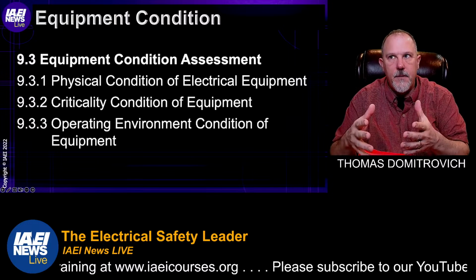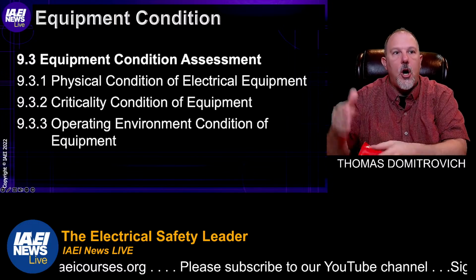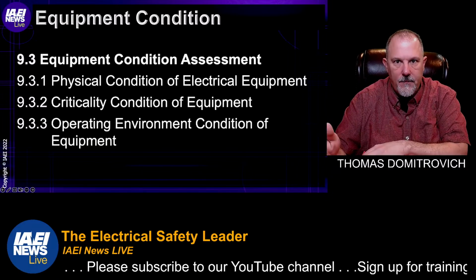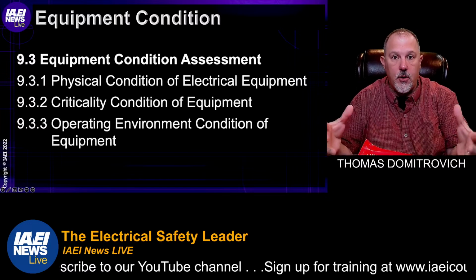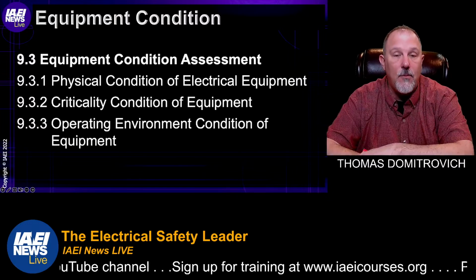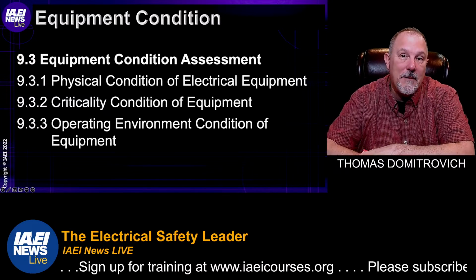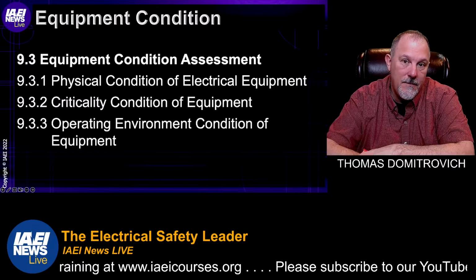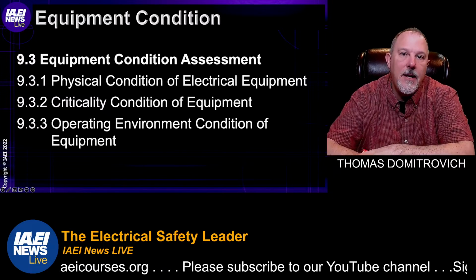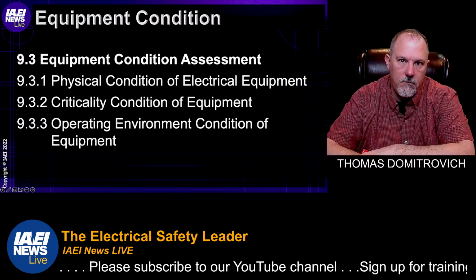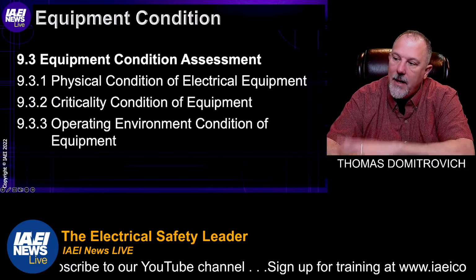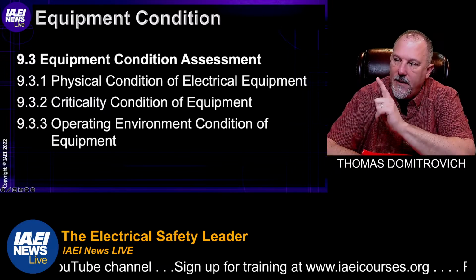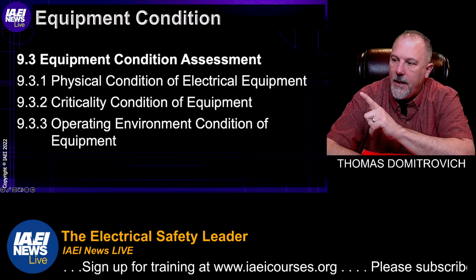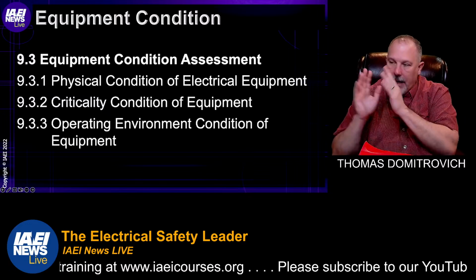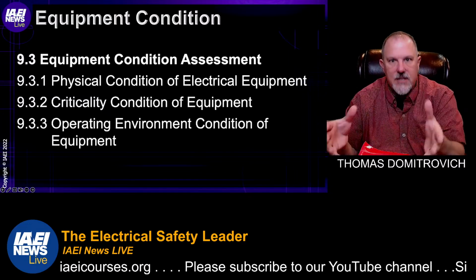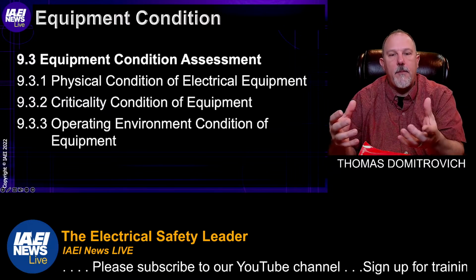So think about a panel board. If I have a panel board installed on a pier in a saltwater environment, and the panel board and its enclosure are listed for that environment, I still might want to increase the maintenance intervals on that equipment. And I don't think I would treat it exactly the same as a panel board in an air-conditioned clean room. You get my drift? So it's a bare minimum requirement. But operating environment condition of equipment, it needs some work. But if your panel board is outside, you're going to probably want to look at that.